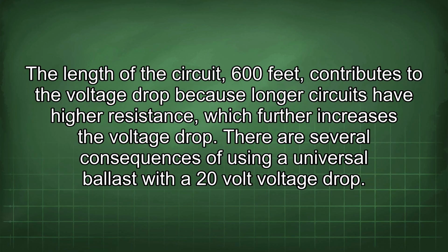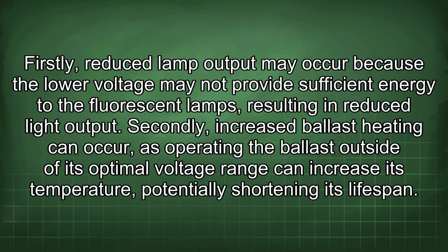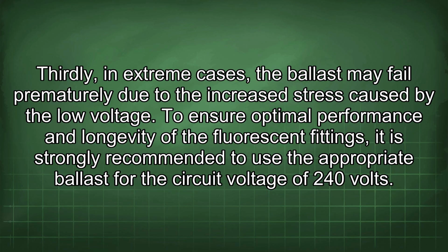long it lasts. The length of the circuit, 600 feet, contributes to the voltage drop because longer circuits have higher resistance, which further increases the voltage drop. There are several consequences of using a universal ballast with a 20-volt voltage drop. Firstly, reduced lamp output may occur because the lower voltage may not provide sufficient energy to the fluorescent lamps, resulting in reduced light output. Secondly, increased ballast heating can occur, as operating the ballast outside of its optimal voltage range can increase its temperature, potentially shortening its lifespan. Thirdly, in extreme cases, the ballast may fail prematurely due to the increased stress caused by the low voltage.